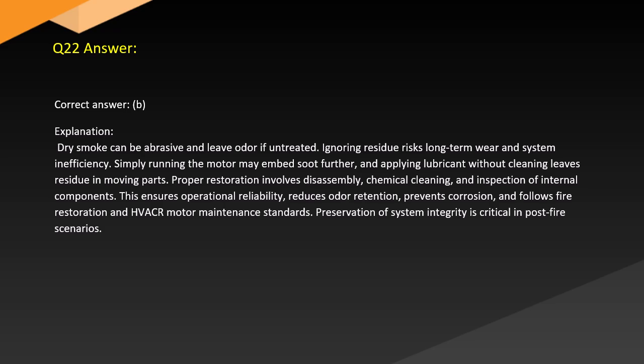Answer. Correct answer: B. Explanation: Dry smoke can be abrasive and leave odor if untreated. Ignoring residue risks long-term wear and system inefficiency. Simply running the motor may embed soot further, and applying lubricant without cleaning leaves residue in moving parts. Proper restoration involves disassembly, chemical cleaning, and inspection of internal components. This ensures operational reliability, reduces odor retention, prevents corrosion, and follows fire restoration and HVACR motor maintenance standards. Preservation of system integrity is critical in post-fire scenarios.